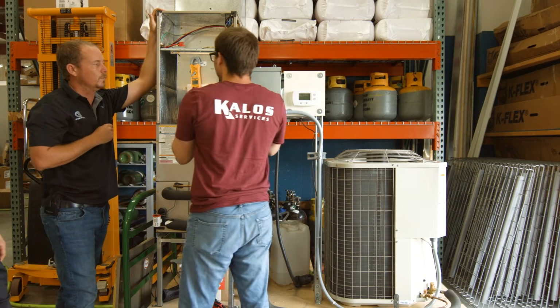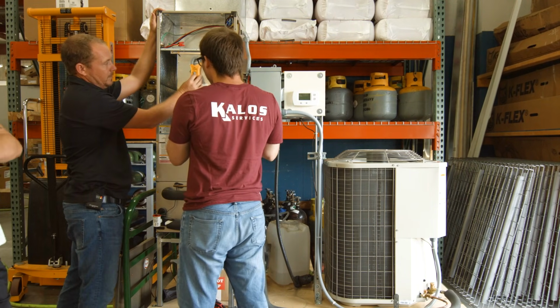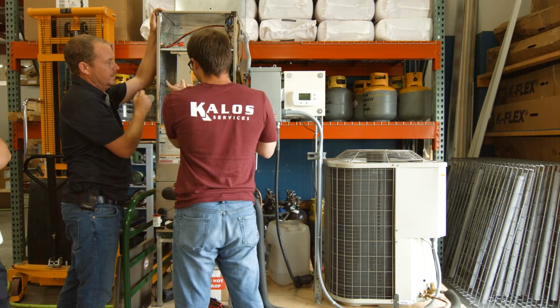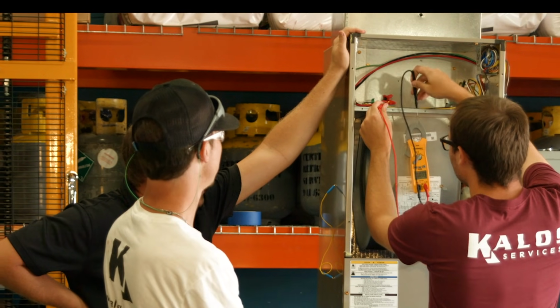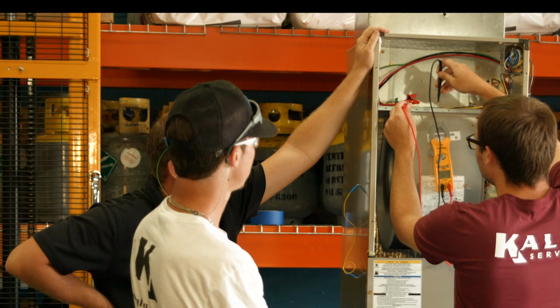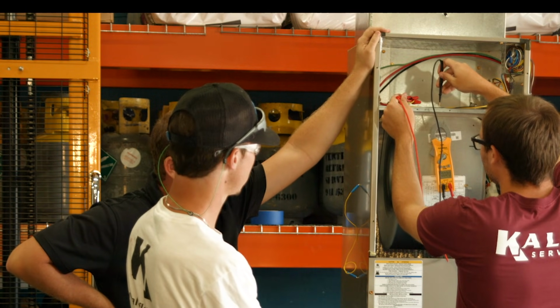So what are we on now? Before you even do that, we're going to put it on the ohm scale. You already did it? I did. Okay, good. So you check each one to ground. That's a safety check, because sometimes you get one, since you could have just one leg that's energized.